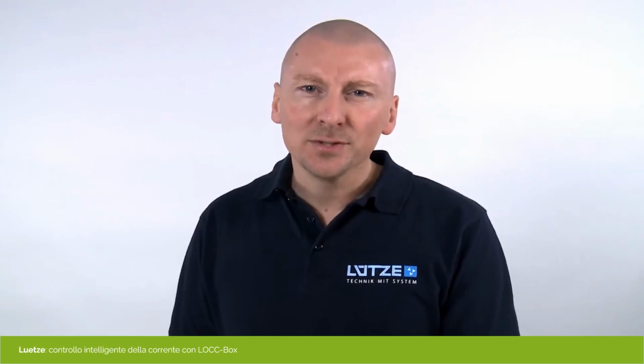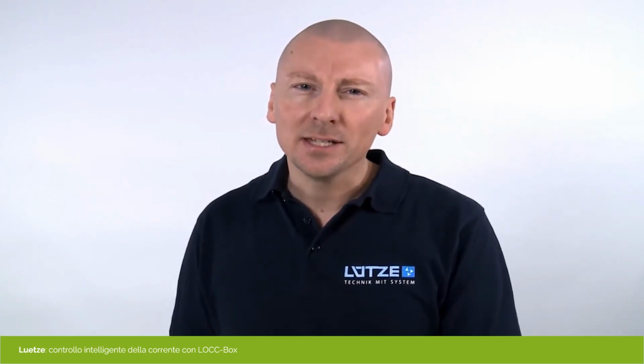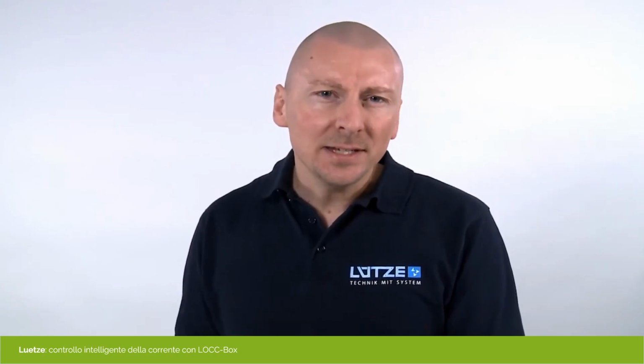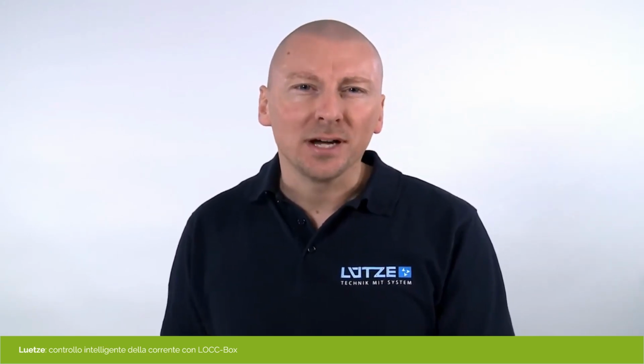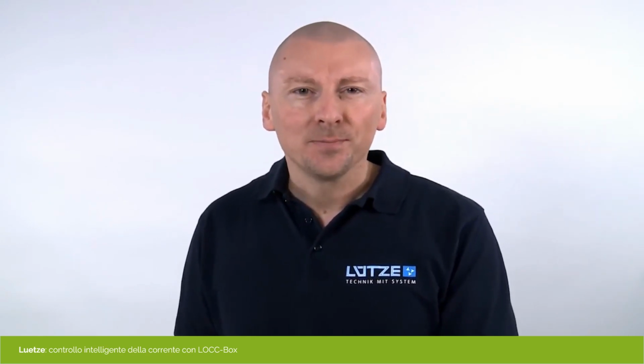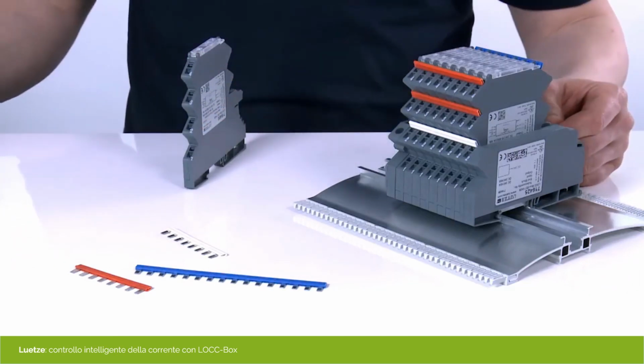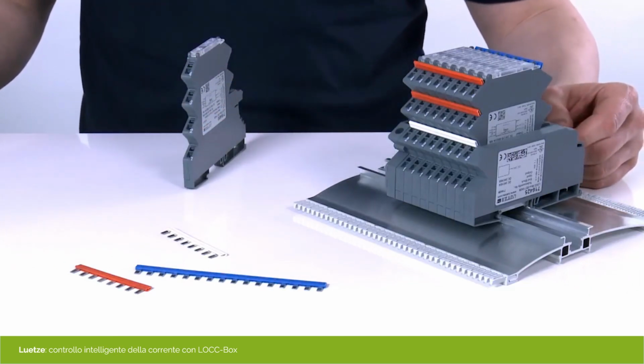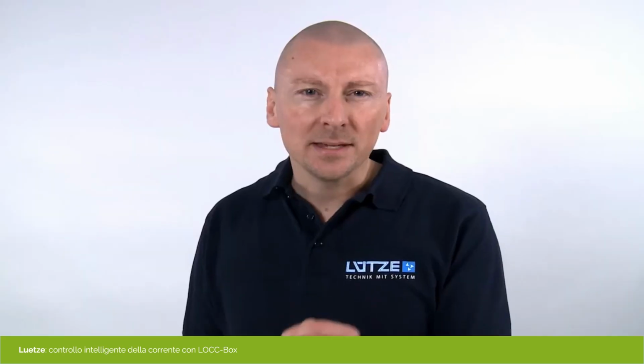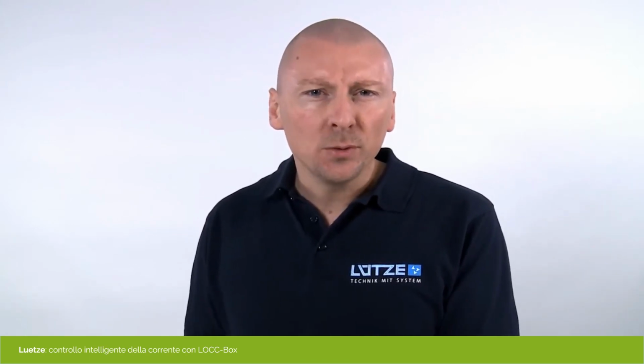If several modules need to be activated and deactivated at the same time, this can be realized with a jumper comb. In the event of a reset, all triggered modules are reactivated again. Connection to a digital output is possible. Terminal 3 reports the operating status of a LOCC-Box and can be connected directly to a digital input of a control unit. This makes single-channel reporting very easy. Only one jumper comb is required for a centralized error message.